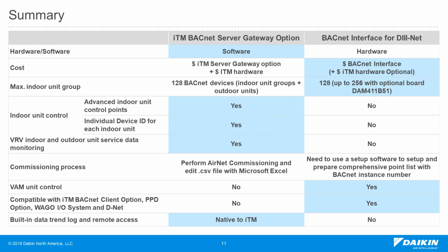And the ITM server gateway cannot be used to control the VAM unit, and it's not compatible with other options of the ITM: the BACnet client option, the PPD option, the WAGO IO system, and DNet monitoring. But the ITM itself actually has the built-in data trend log and remote access, which we believe gives more advantage to the users. So as you can see, if you try to choose which product you want to use for your project, the ITM BACnet gateway definitely has more advantage when it comes to controls, but it also has some limitations. For example, if you have a multi-tenant building that needs the ITM PPD option, you can only go with the BACnet gateway because the BACnet server option is not compatible with the PPD option. So this is a summary of comparing these two products.